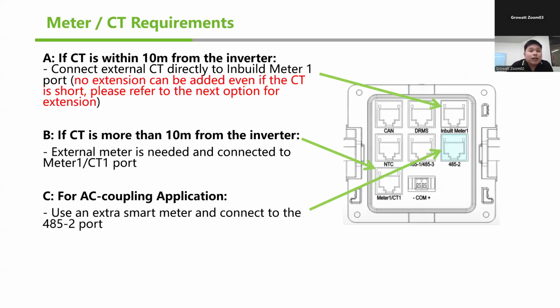So one key thing here when it comes to the installation, if the CT is within 10 meters from the inverter, connect the external CT directly to Inbuild Meter 1 port, which is in the connection box. So note there's one important thing here. If the CT is within 10 meters, but it is too small or too short, you might need an extension. So note that if an extension is required, you have to move to option B, which means that whenever an extension is required, even though it's within 10 meters, you still need an external smart meter to be installed in the system. And when that happens, you have to select meter 1 or CT1 port. So make sure that no extension can be added, even if the CT is very short.